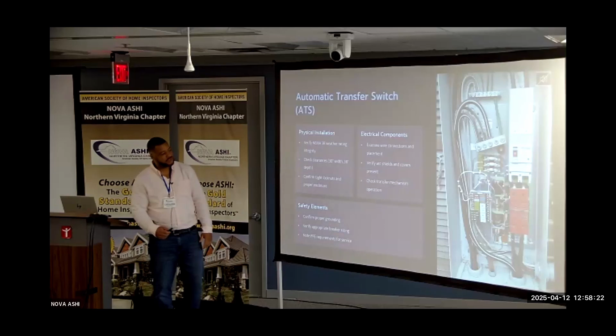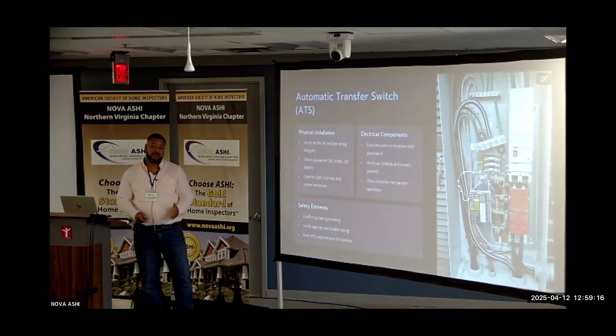I would suggest and recommend that you turn it off with the shield, the dead front, on it, as I mentioned earlier. You don't want to take those risks. If you take the cover off and you have the dead front visible, you have this little yellow handle. Sometimes those transfer mechanisms fail, and if it fails and someone wants to have power, they can manually transfer it. You stick this little handle into the yellow piece, into this little hole right there, and pull it down, and you can transfer power. Let's say it doesn't transfer power back when the electrical utility is restored, you can manually transfer it as well. So this is a manual system as well.